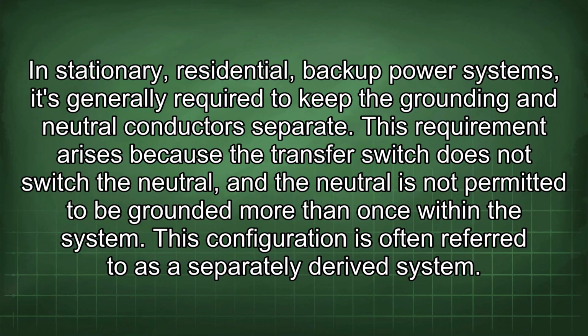In stationary, residential, backup power systems, it's generally required to keep the grounding and neutral conductors separate. This requirement arises because the transfer switch does not switch the neutral, and the neutral is not permitted to be grounded more than once within the system. This configuration is often referred to as a separately derived system.